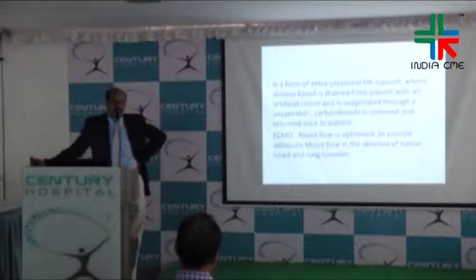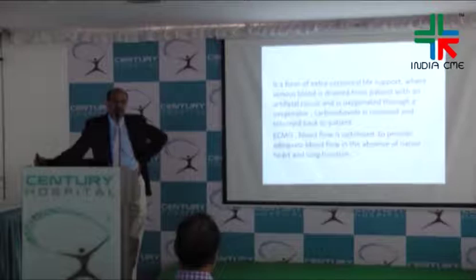When we say VA ECMO, it's more like a long-term cardiopulmonary bypass, which most cardiac surgeons are used to. There's a basic difference between the cardiopulmonary bypass machine used in theaters and the ECMO machine. First and foremost, it's short-term in cardiac theaters - the oxygenator lasts about 8 to 10 hours, sometimes a bit longer, but the maximum is 8 to 10 hours.